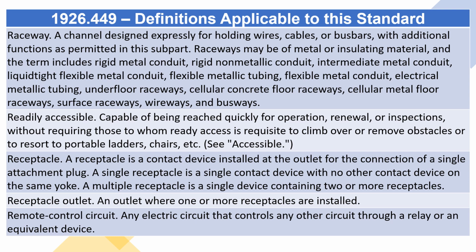Readily accessible. Capable of being reached quickly for operation, renewal, or inspections, without requiring those to whom ready access is requisite to climb over or remove obstacles or to resort to portable ladders, chairs, etc. See accessible. Receptacle. A receptacle is a contact device installed at the outlet for the connection of a single attachment plug. A single receptacle is a single contact device with no other contact device on the same yoke. A multiple receptacle is a single device containing two or more receptacles. Receptacle outlet. An outlet where one or more receptacles are installed.